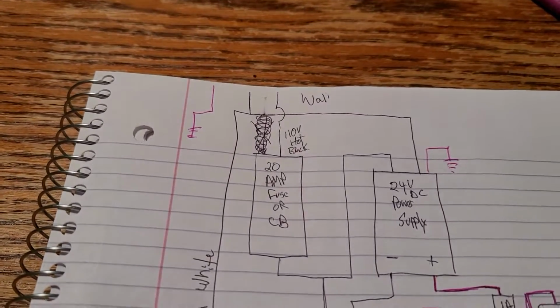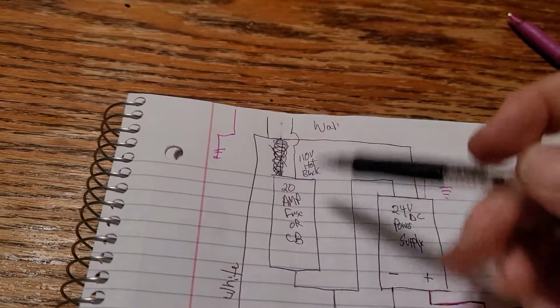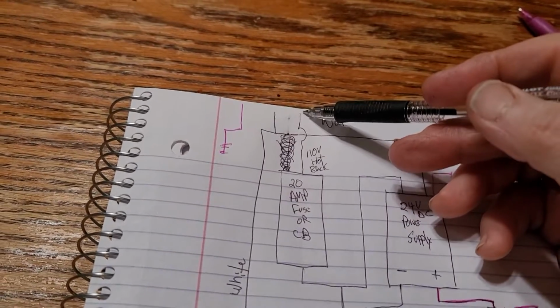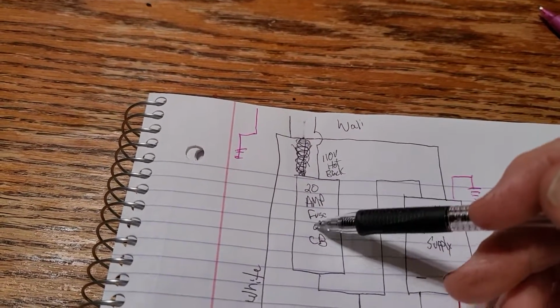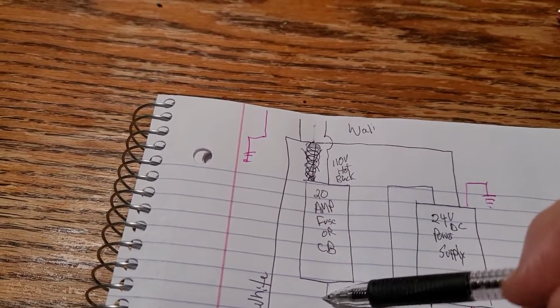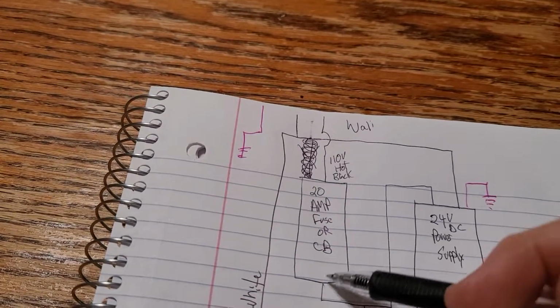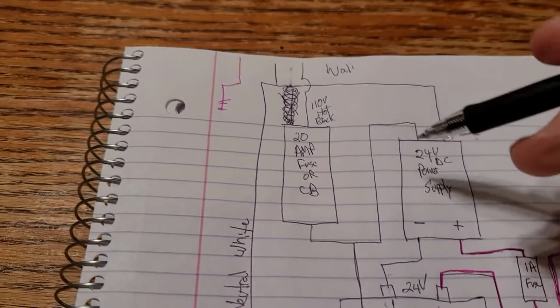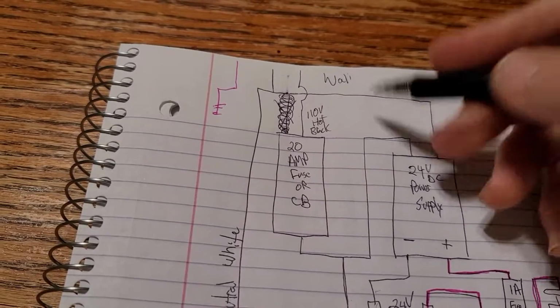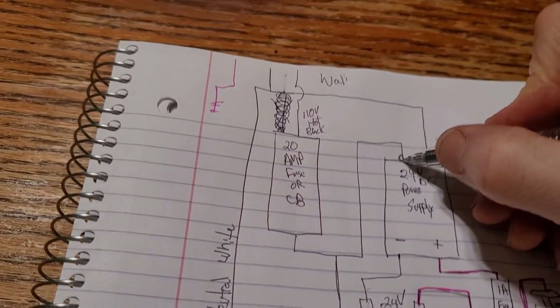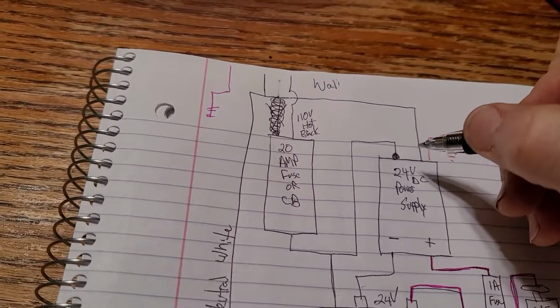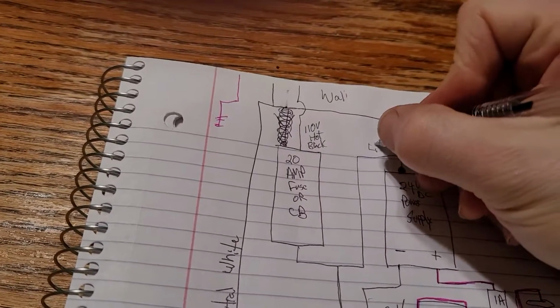I put fuse, but you can buy a circuit breaker. Those are probably newer, they might be more expensive, I don't know. But you want to run the power from the wall through that circuit breaker or that fuse. And then you're going to run it to two places. You're going to connect it to the AC hot input on the 24 volt power supply. That's going to say line.